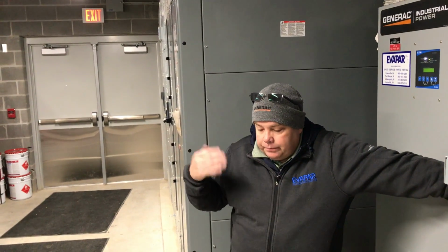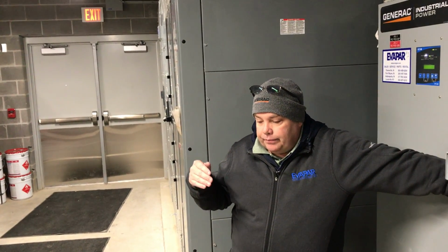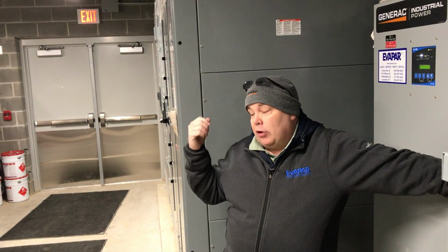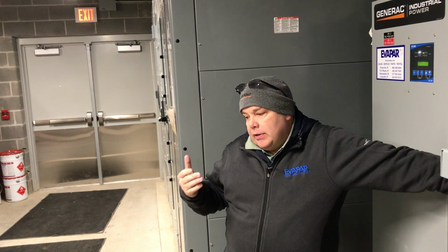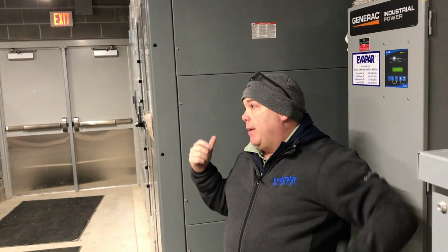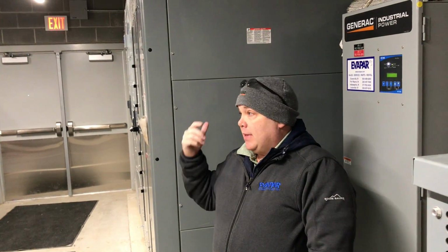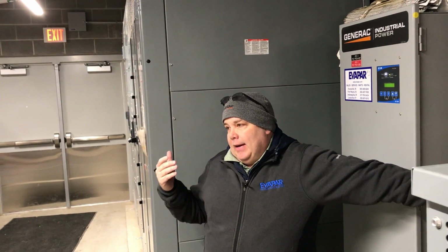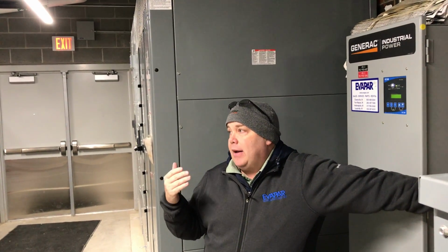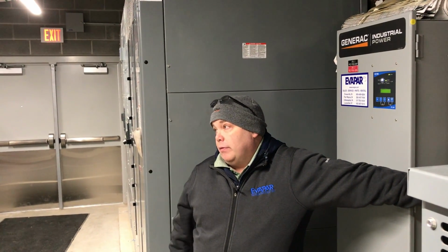Okay, on the screen now. So what it is, so the power's lost, generator starts. There's an alternator out there that's charging the batteries. But since it's not backed up, there's no power going to the battery charger because it's not on a panel that's being backed up. So the generator's seeing that there's no battery charger. It's a safe way to think, because that's one of the most critical things, the battery charger. So it's just saying that it's not seeing voltage to the battery charger.